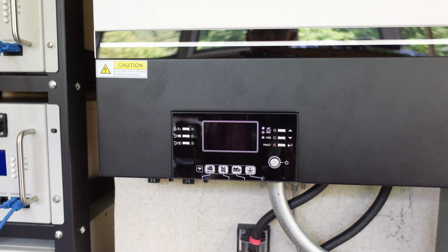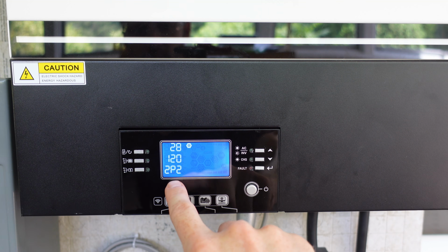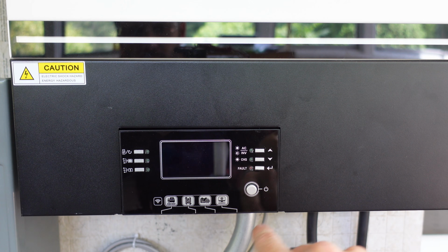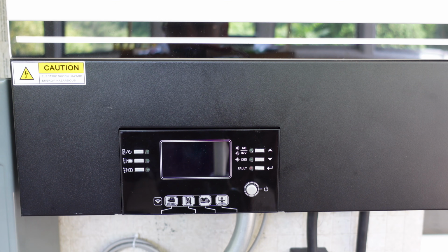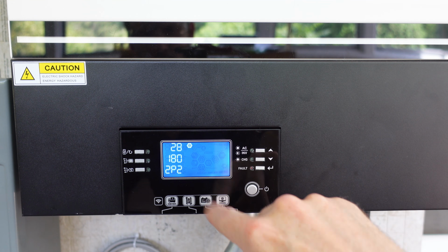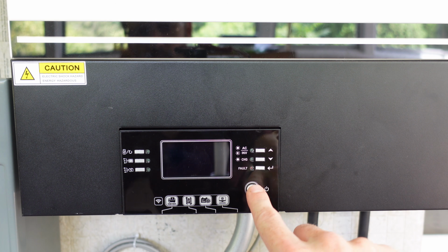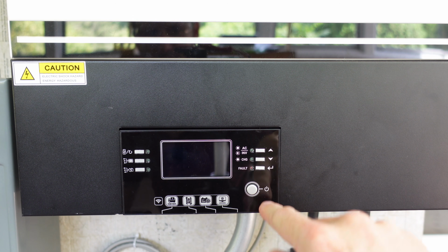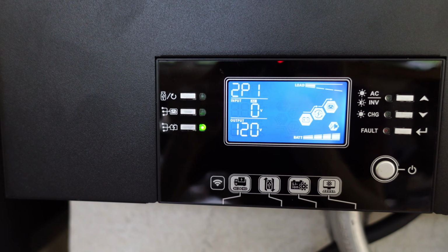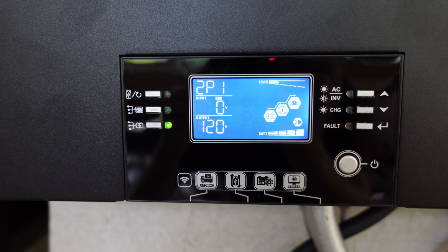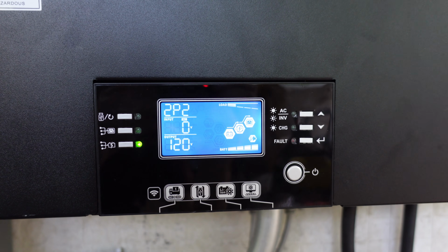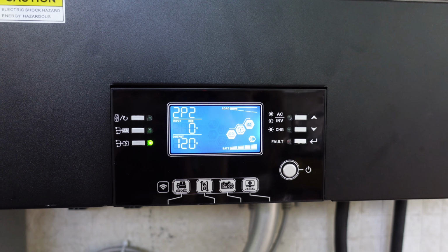Okay, and you see how fast that shut down there? And this one gets set to 2P2, 180 degrees difference. Oh, and you see I wasn't fast enough, so I'm going to have to do that again super quick here. Got it, 28, 180, 2P2. So now we're ready to turn both of these inverters on, and we want to double check that that setting has saved. Alright, so on the left inverter I see the top left says 2P1, and on the right inverter I see it says 2P2, so we know it saved our settings correctly.